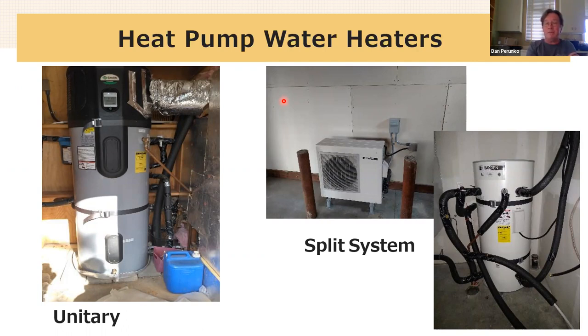And every time that I've been in that scenario, the machine was installed in a closet with no access to air where it could absorb heat. So of course it doesn't work, right? It has to be able to get the heat from somewhere. This is a split system. This is a Sanden split system heat pump water heater. These are cool. They use carbon dioxide as the refrigerant. So the refrigerant has much lower global warming potential than the other machines.